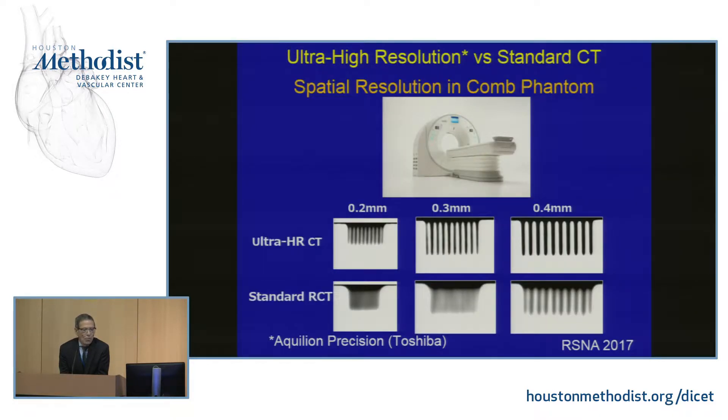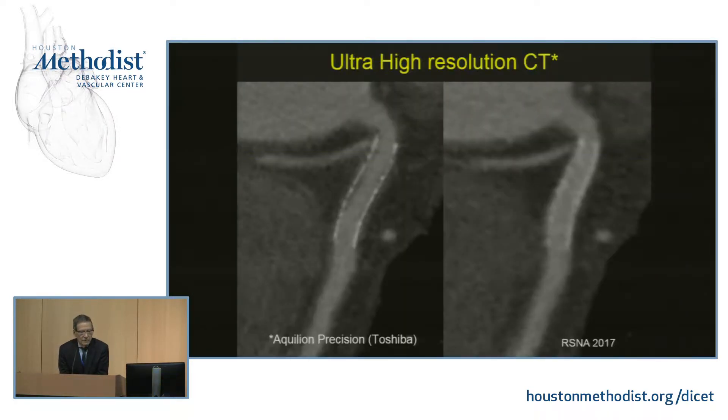Here we see a comb phantom with this ultra-high resolution CT on top and standard CT on the bottom. At the 0.2-millimeter level we can distinguish the prongs of the comb, where standard technique shows only a blur. These slides were lent by Dr. Sagniko Moriyama, who has had the most experience with this technique. We see a stent where on the right there appears to be no abnormality, but with the high-resolution method a mild narrowing underneath the stent in the coronary is visible.